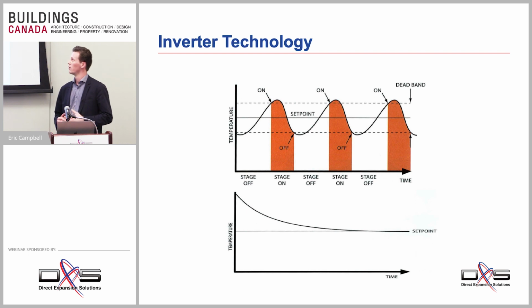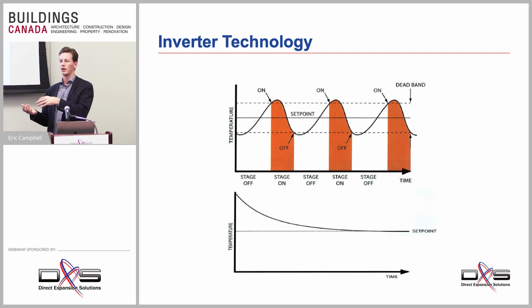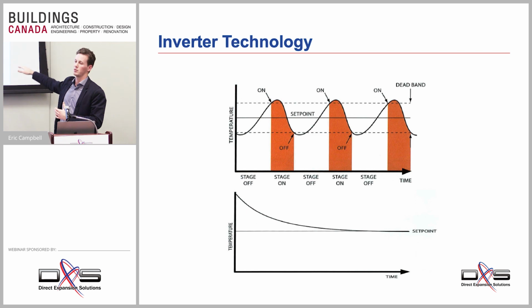So inverter technology. The simplest way to think about inverter technology is you take a simple on-off system, which allows your set point in the space, meaning the temperature in the space, to fluctuate a lot as the system kicks on and it cools for a while, and then it'll turn off and the space heats back up. And as we change the modulation time of the time off versus the time on, we try to leave it as continuous as possible, then we can achieve the inverter technology that allows us to maintain temperature as close as possible to set point. So we eliminate the on and the off, and that actually allows us to run far more efficiently. So the inverter technology is what allows the compressor in a heat pump to run most efficiently.